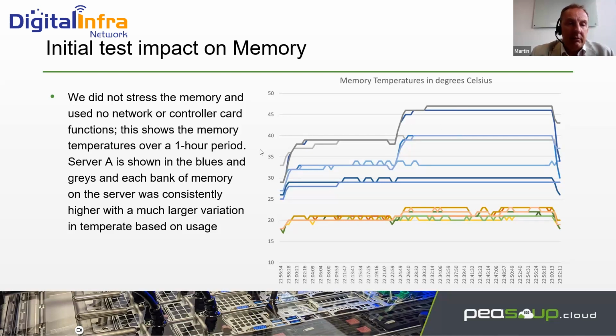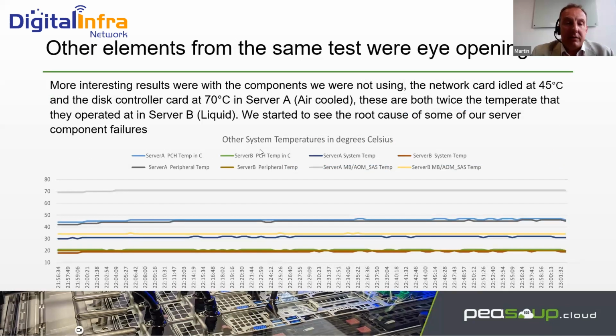More interestingly were the things we weren't testing. We'd never really delved into exactly what a server does - we're a consumer. But looking at this, we saw that network cards not in use were running at about 45 degrees in air, versus around 20 in liquid, which we'd expect given the liquid temperature. But the controller card, also not in use, was running double the temperature in air compared to liquid.